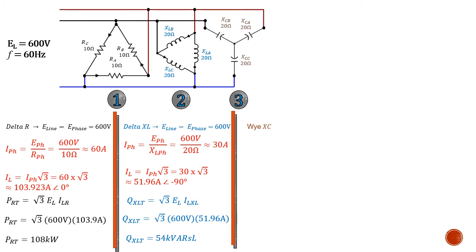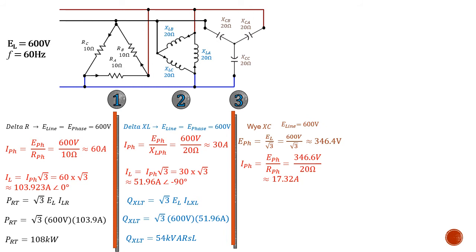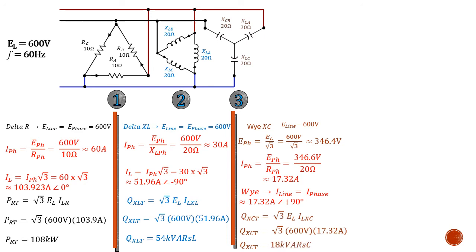Moving on to our third section: the Y-connected capacitance. We have 600 volts line voltage, but since it's a Y, we compensate for the phase voltage. 600 divided by root 3 gives us approximately 346.4 volts per phase across each capacitive component. That works out to about 17.32 amps per phase in our capacitive circuit. Since it's a Y, line currents and phase currents are the same, so we have 17.32 amps capacitive, which means it leads by 90 degrees. With those values in hand, we calculate our capacitive reactive power, which comes out to be about 18 kVArs.